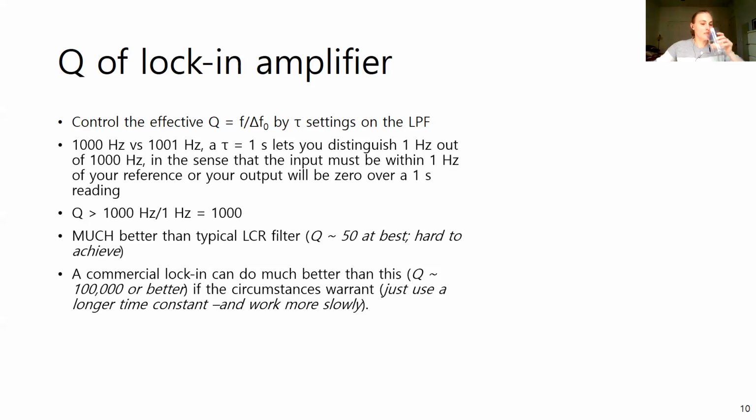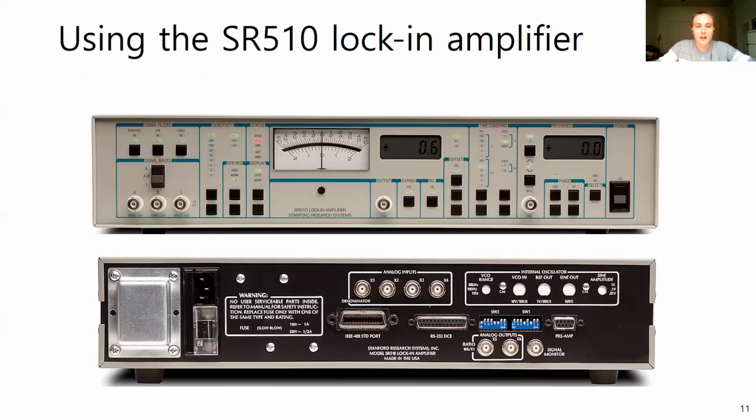But the lock-in, you can get much higher, 10 to the 5th or so quality factors, and it's really just by pushing buttons. It's not digging through all the electrical components and stuff.